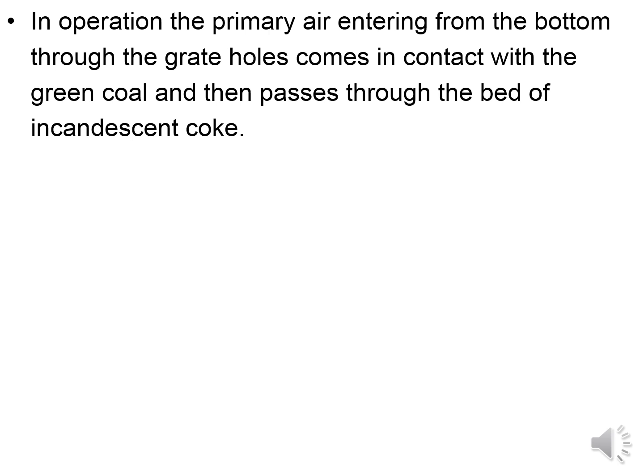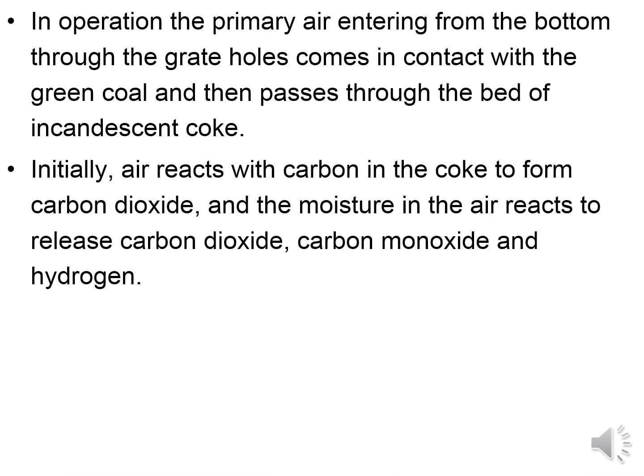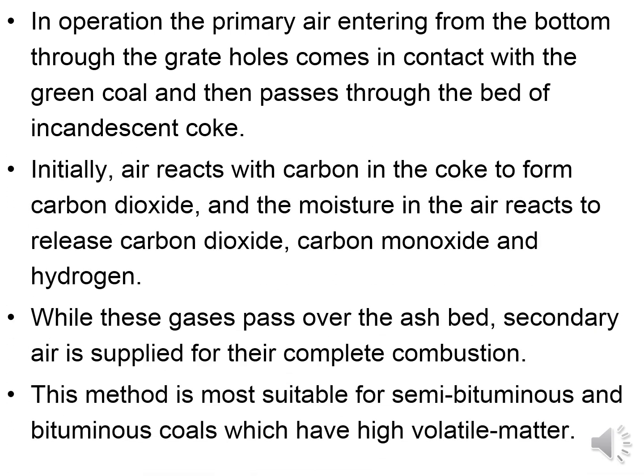In under-feed stoker operation, primary air entering from the bottom through the grate comes in contact with green coal and then passes through the bed of incandescent coke. Air initially reacts with carbon in the coke to form carbon dioxide, and moisture of the air reacts to release carbon dioxide, carbon monoxide, and hydrogen. This method is most suitable for semi-bituminous and bituminous coals, which have higher volatile content.